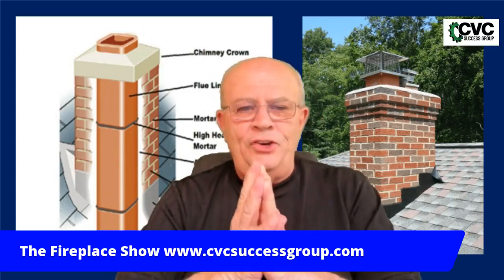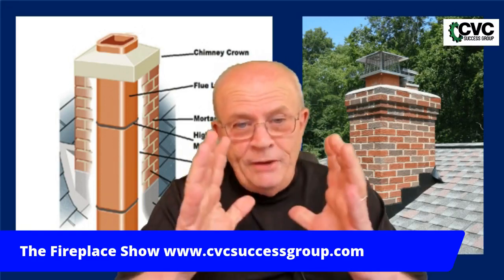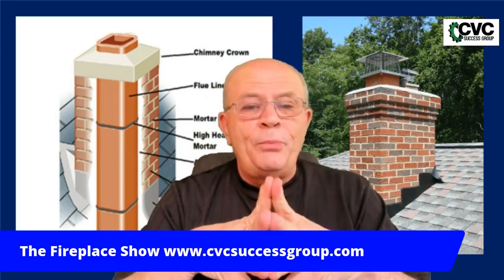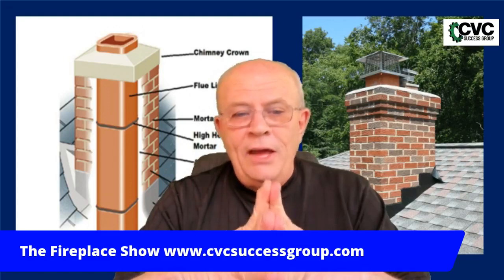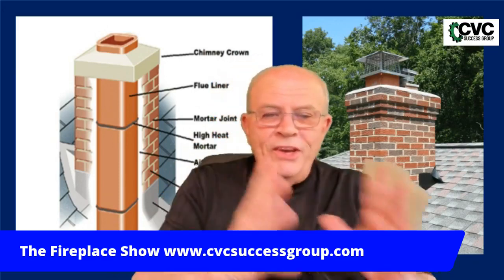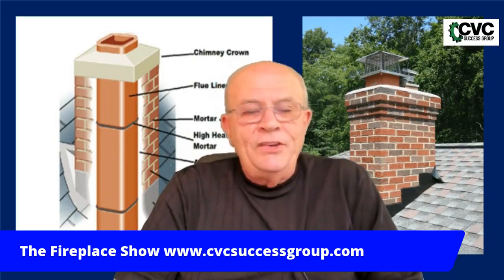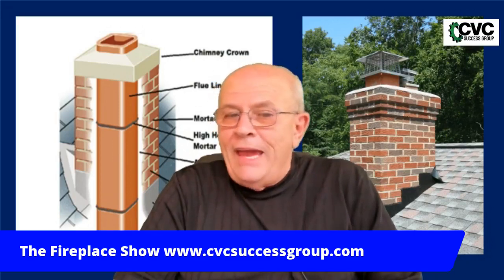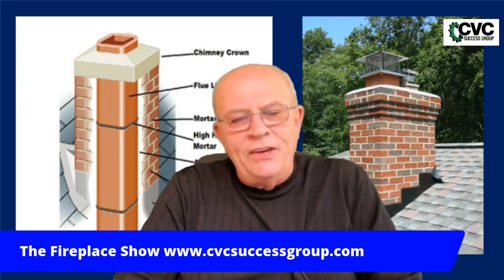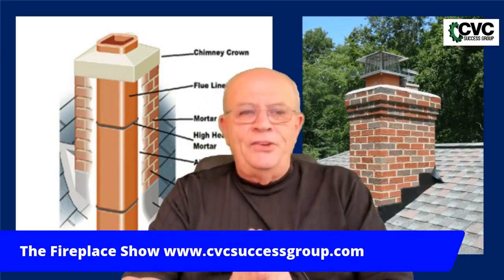A lot of people think clay tile is there strictly for safety. However, clay tile is actually used to protect the fragile chimney itself — the masonry materials — from the acid attack of the flue gases. Research done by the United States government through the 1940s by various testing agencies further confirmed the problem of acids in chimneys. The safety of the chimney is contingent upon its clearances to surrounding materials.